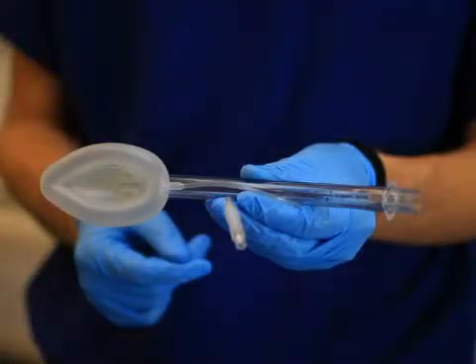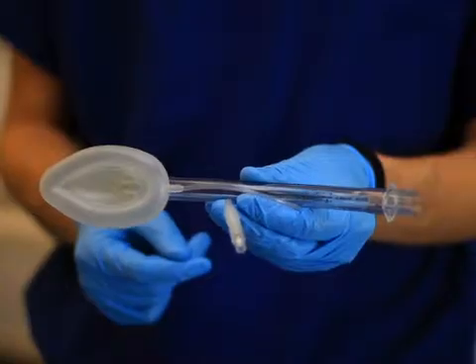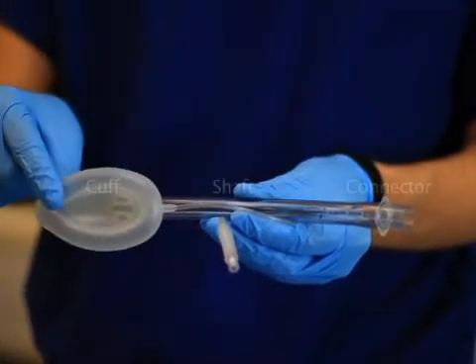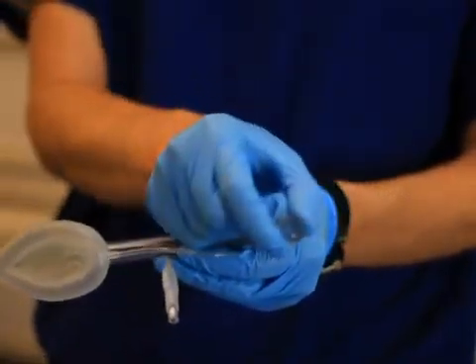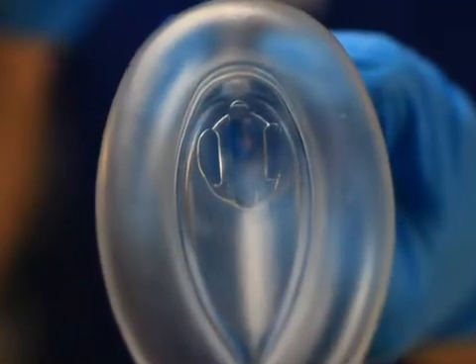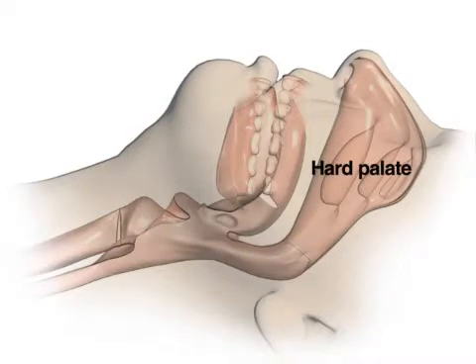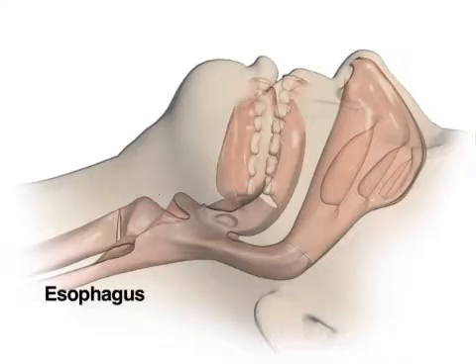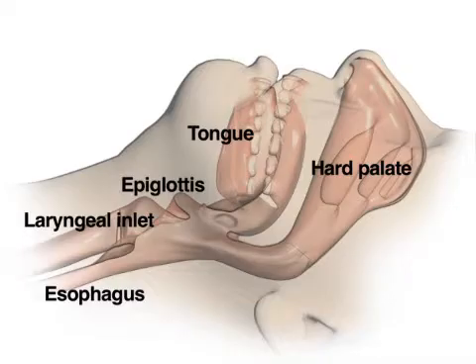An adult-sized laryngeal mask airway is a flexible breathing tube of approximately 25 centimeters in length with an inflatable bladder or cuff on its distal end. The proximal end has a standard 15-millimeter connector that allows attachment to any ventilation system. Air exchange occurs through the aperture on the distal end of the tube. This illustration shows the tongue, hard palate, epiglottis, esophagus, and laryngeal inlet. Review of these structures is helpful for understanding proper placement and potential difficulties.